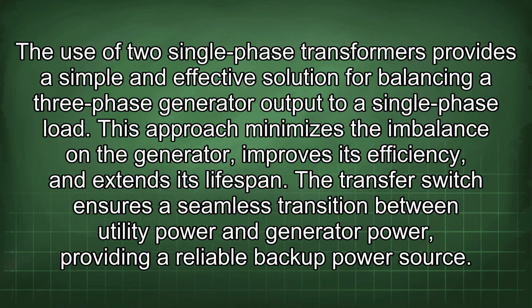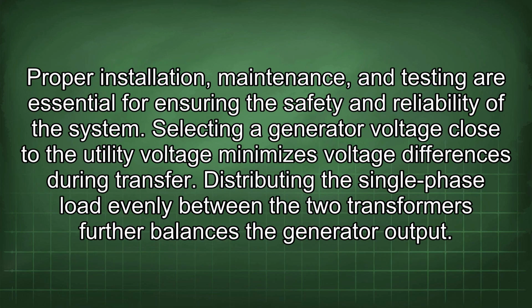The use of two single-phase transformers provides a simple and effective solution for balancing a three-phase generator output to a single-phase load. This approach minimizes the imbalance on the generator, improves its efficiency, and extends its lifespan. The transfer switch ensures a seamless transition between utility power and generator power, providing a reliable backup power source. Proper installation, maintenance, and testing are essential for ensuring the safety and reliability of the system.